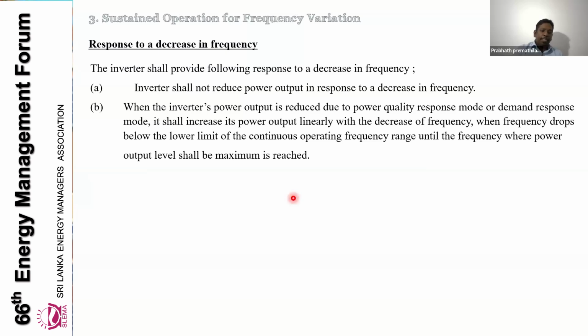In addition to that, there are voltage disturbances and frequency disturbances. Some standards also talk about sustained operation for frequency variation. Now I am going to explain how frequency disturbance ride through happens here. When the system frequency is decreasing, the inverter shall not reduce its power output in response to the decrease in frequency.